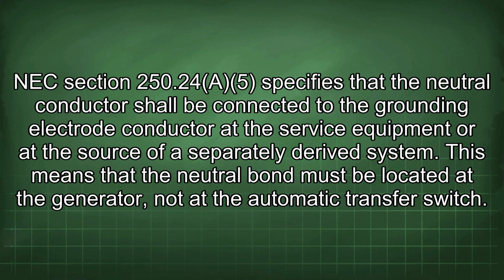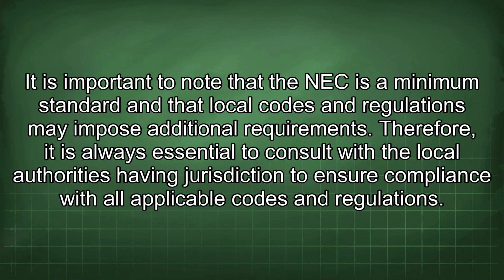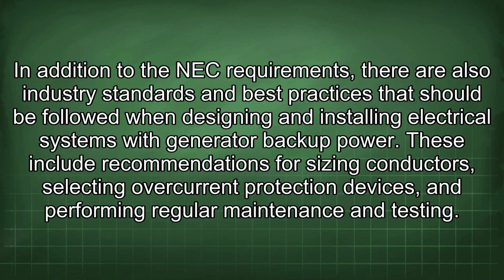This means that the neutral bond must be located at the generator, not at the automatic transfer switch. It is important to note that the NEC is a minimum standard and that local codes and regulations may impose additional requirements. Therefore, it is always essential to consult with the local authorities having jurisdiction to ensure compliance with all applicable codes and regulations. In addition to the NEC requirements, there are also industry standards and best practices that should be followed when designing and installing electrical systems with generator backup power.